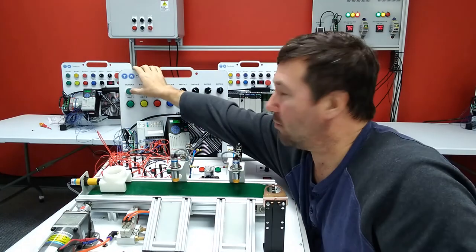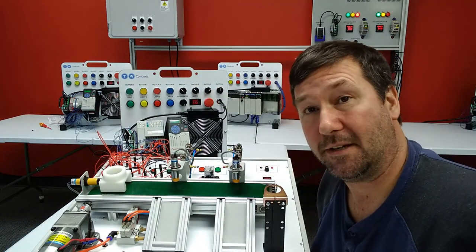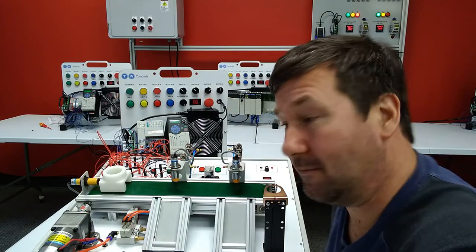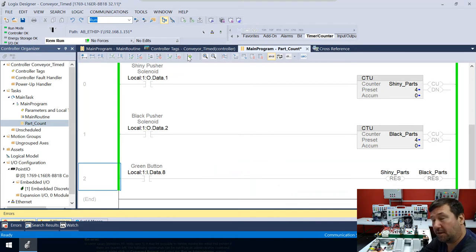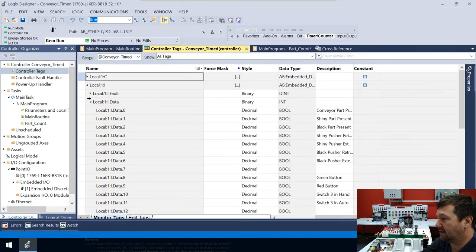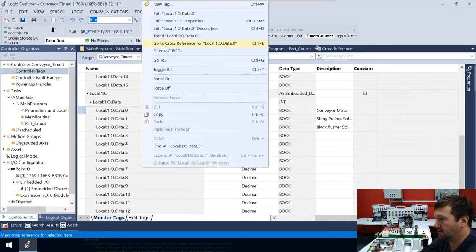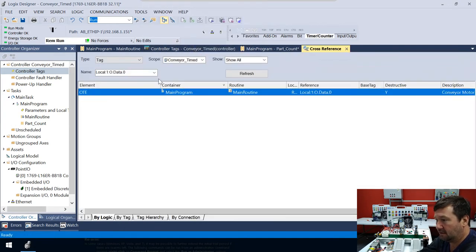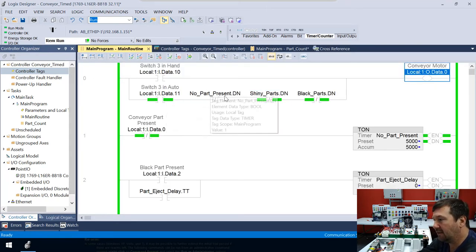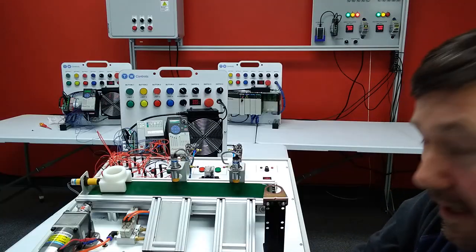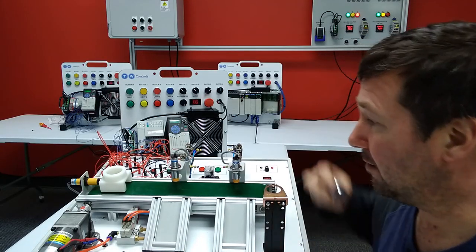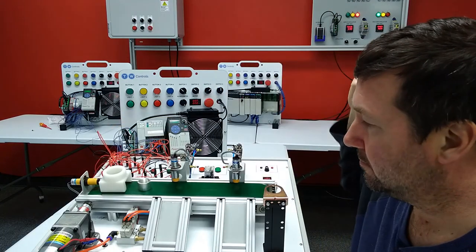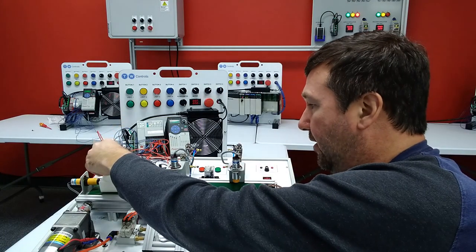All right. So we're ready to go. And we're going to hit a green button. And nothing's going to happen. Now, why is nothing happening? Well, let's go find out. So do you remember how to use the cross-reference to find that output? Or do you remember where it is? Either go to your controller tags and find that conveyor motor and cross-reference it, or just remember that it was in the main routine. It's rung zero. And we can look now and see the thing that's holding us off now is this no part present. And so that's it. It's looking for a part. And there is no reason for the conveyor to start back up if there isn't a part. So we'll drop a part in now. Drop another part in.